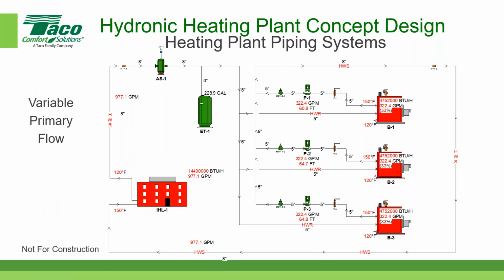Someone's asking about consideration of buffer tanks and sizing them. We have a nice recommendation on our website for sizing buffer tanks, but I think the best answer to that is check your boiler manufacturer, how much volume of water you need. Yeah, exactly. That's why it's so important to work closely with the type of boiler and the configuration of how you want it to operate in the system. Because the boiler manufacturer is going to, like you just said, Brett, set the parameters for how much volume of water you're going to need in the system and how big the buffer tank is going to be relative to the rest of the volume of the water in the system.